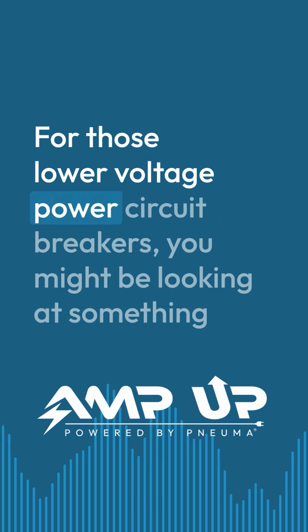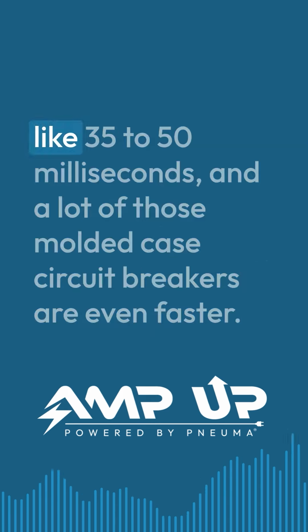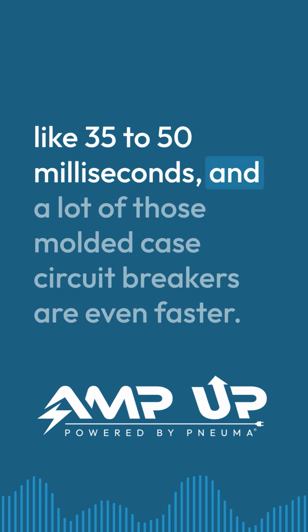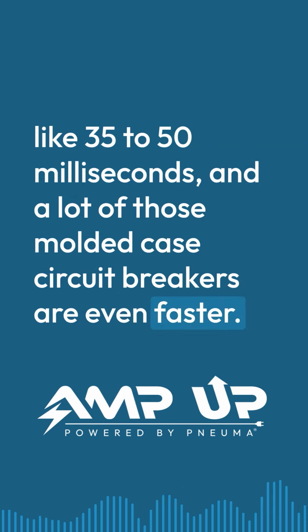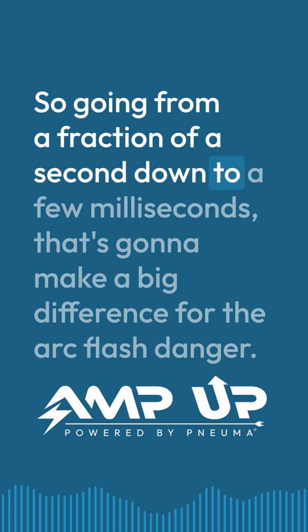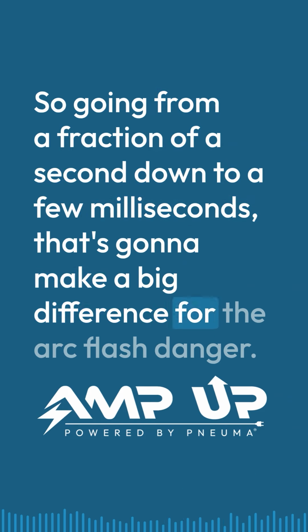For those lower voltage power circuit breakers, you might be looking at something like 35 to 50 milliseconds. And a lot of those molded case circuit breakers are even faster. So going from a fraction of a second down to a few milliseconds, that's going to make a big difference for the arc flash danger.